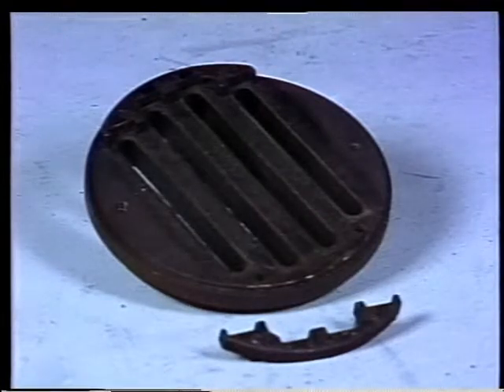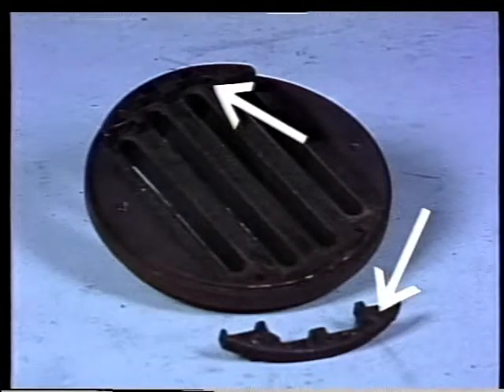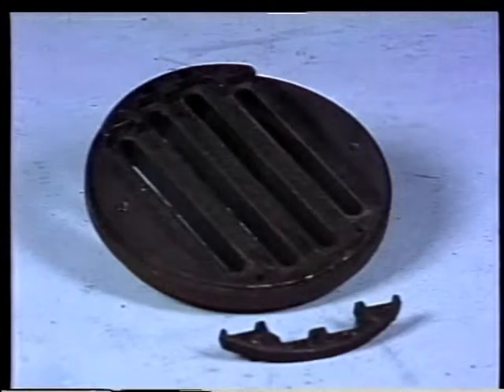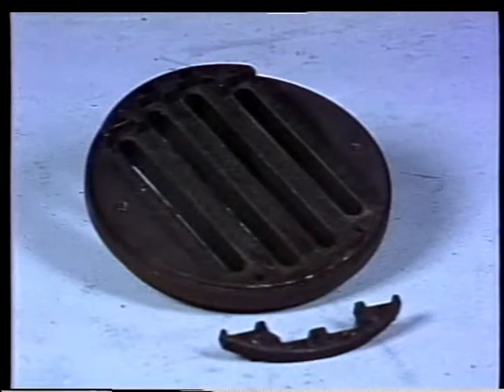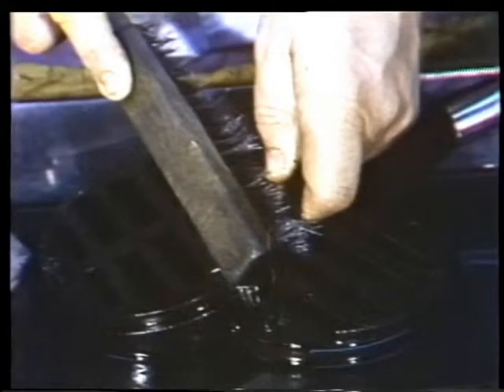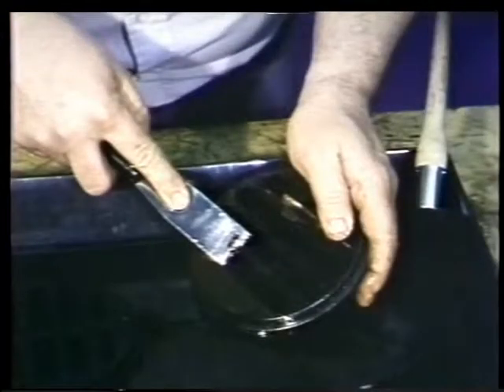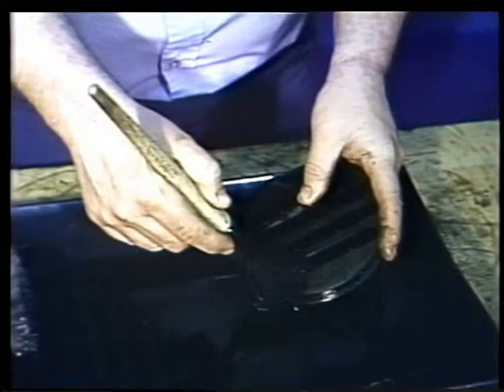The next step in this operation is to pry out the channel guides. Once that's done, you're ready to clean all the valve surfaces. To do this, you use a solvent and a wire brush or scraper. But it must be done carefully. Avoid gouging the metal while scraping. And be sure to use an approved solvent. For example, do not use a flammable solvent. Heat from the action of the compressor could cause a solvent to ignite or possibly explode.